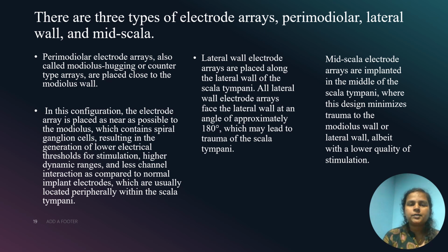In this configuration, the electrode array is placed as near as possible to the modiolus, which contains spiral ganglion cells, resulting in the generation of lower electrical thresholds for stimulation, higher dynamic ranges, and less channel interaction as compared to normal implant electrodes, which are usually located peripherally within the scala tympani. Next are lateral wall electrode arrays that are placed along the lateral wall of the scala tympani. All lateral wall electrode arrays face the lateral wall at an angle of approximately 180 degrees, which may lead to trauma of the scala tympani.